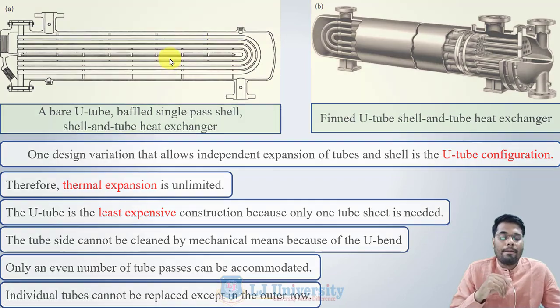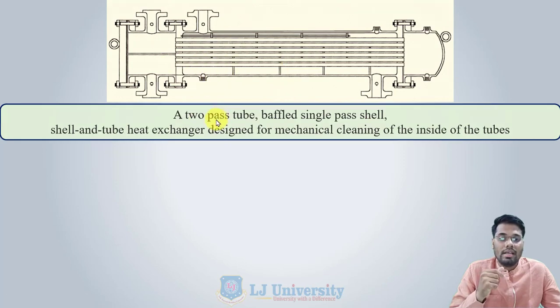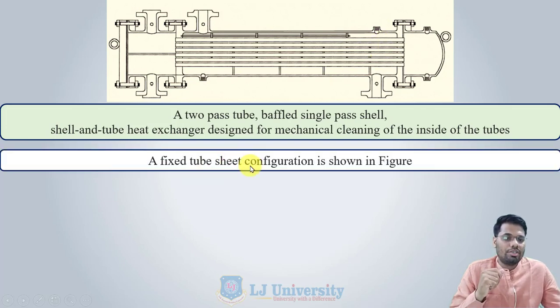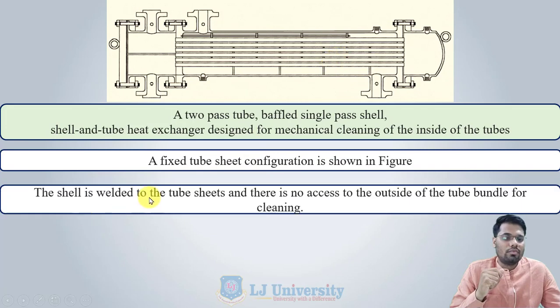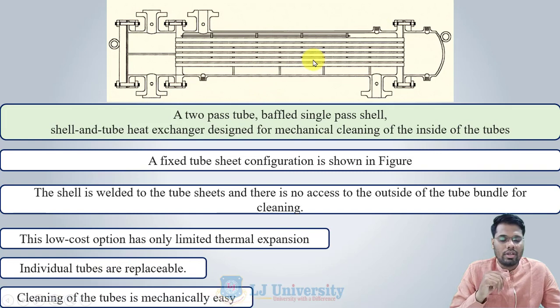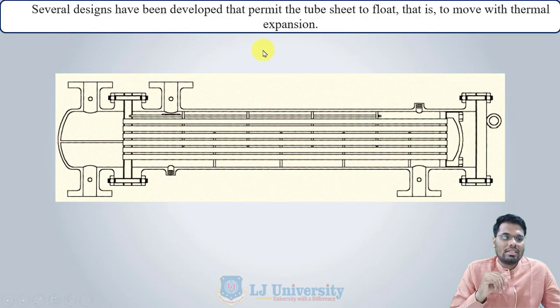The next arrangement is a two-pass tube, baffled single pass shell and tube heat exchanger, designed for mechanical cleaning of the inside of the tubes. A fixed tube sheet configuration is shown where the shell is welded to the tube sheet, so there is no access to the outside of the tube bundle for cleaning. This is a low-cost option with only limited thermal expansion, but individual tubes are replaceable and mechanical cleaning of the tube interior is easy.